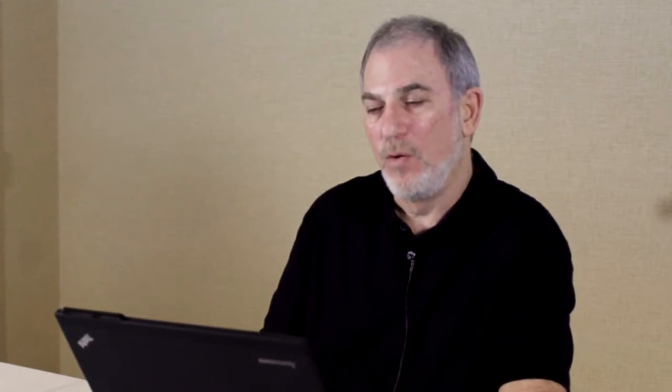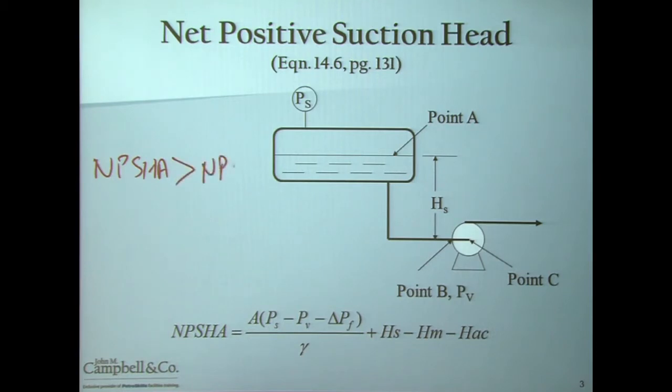Today, we will focus on the concept of net positive suction head available. One of the key points in understanding pumps is that the net positive suction head available must be greater than the net positive suction head required. The net positive suction head required comes from the vendor. The net positive suction head available comes from you.